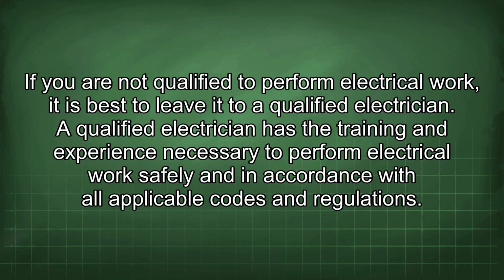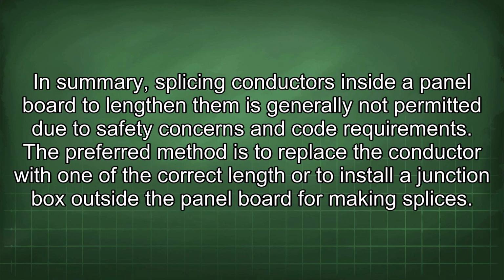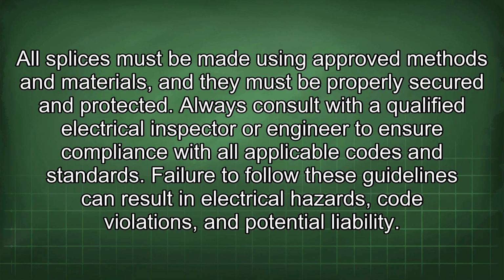In summary, splicing conductors inside a panel board to lengthen them is generally not permitted due to safety concerns and code requirements. A preferred method is to replace the conductor with one of the correct length or to install a junction box outside the panel board for making splices. All splices must be made using approved methods and materials, and they must be properly secured and protected. Always consult with a qualified electrical inspector or engineer to ensure compliance with all applicable codes and standards.